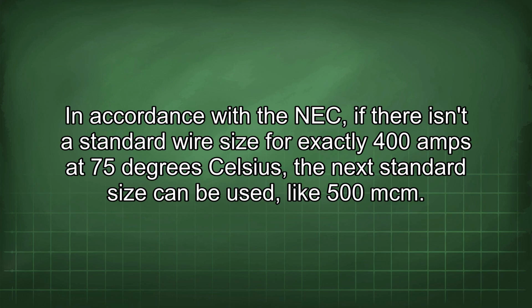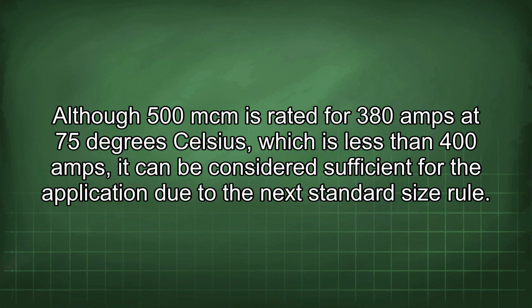In accordance with the NEC, if there isn't a standard wire size for exactly 400 amps at 75 degrees Celsius, the next standard size can be used, like 500 MCM. Although 500 MCM is rated for 380 amps at 75 degrees Celsius, which is less than 400 amps, it can be considered sufficient for the application due to the next standard size rule.